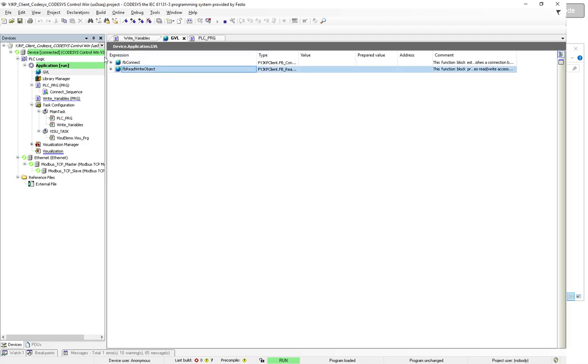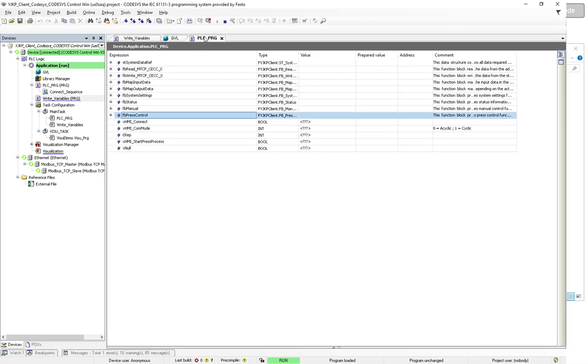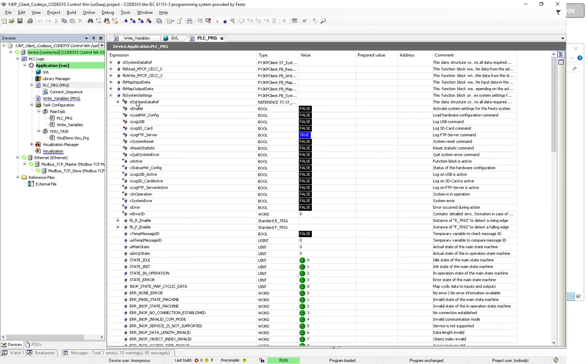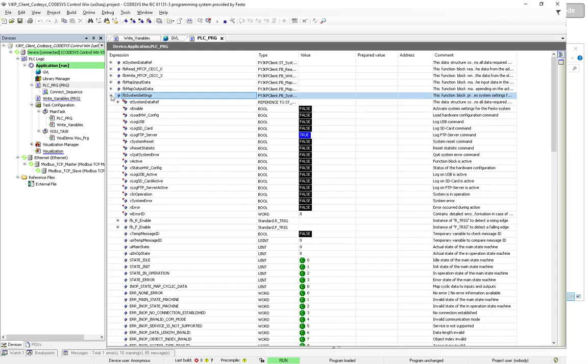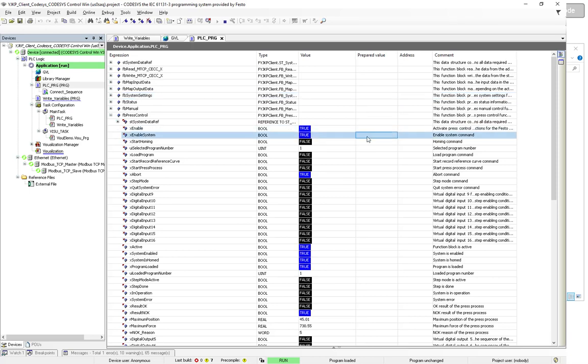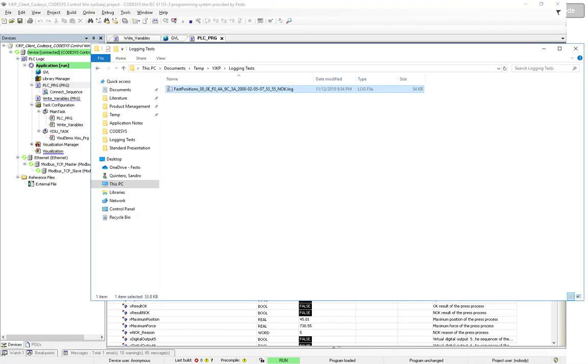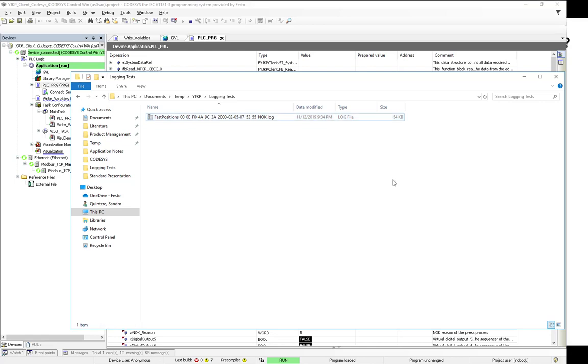Let's go back to FB Connect, switch back to cyclic, and go back to the press control program. I make sure the log FTP server bit is set — and on the web visualization I see the green indicator, so it is logging. I enable the press control function block, enable the system — it's already homed — so I start the press process. After it's done, a new log file appears. Opening it, let's look at the variables: 83, 65, and 49. These three values.